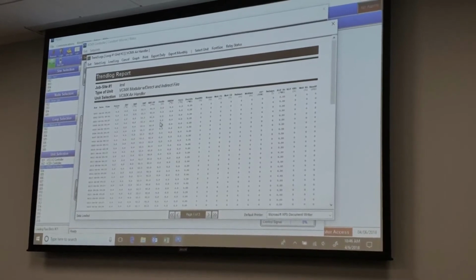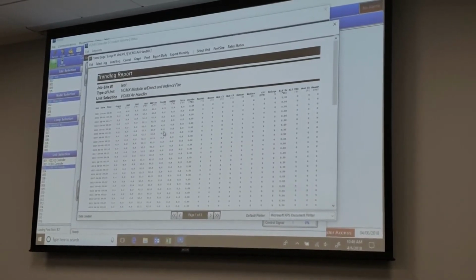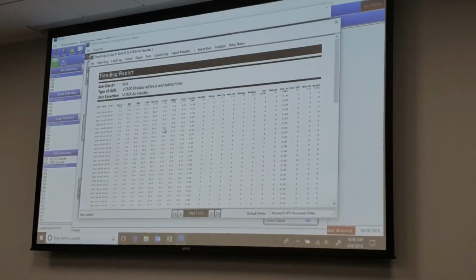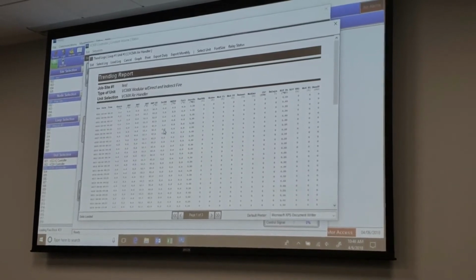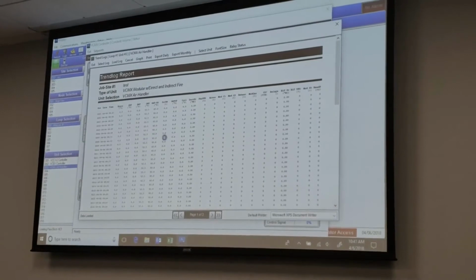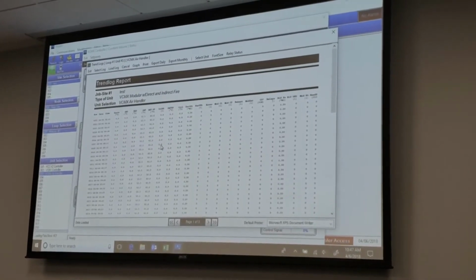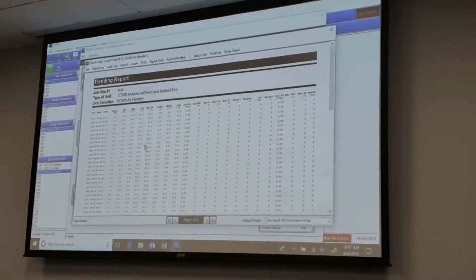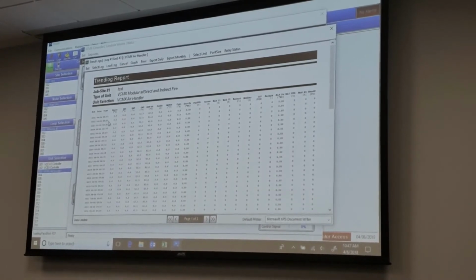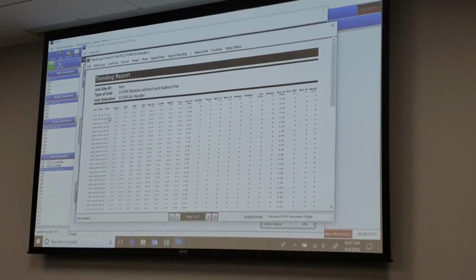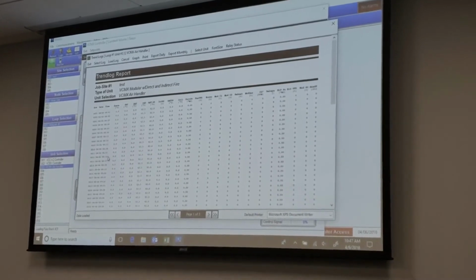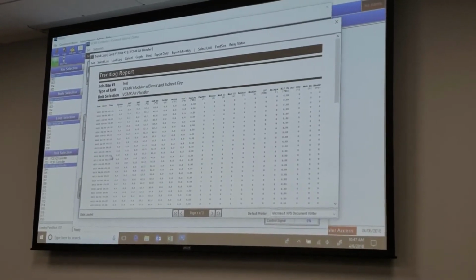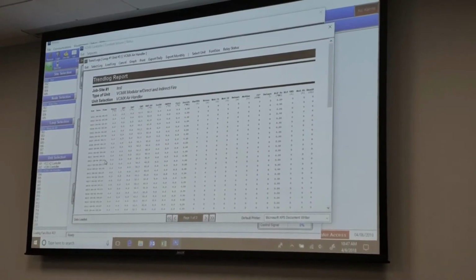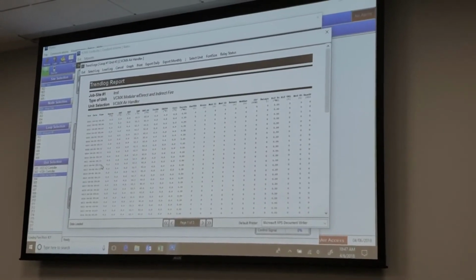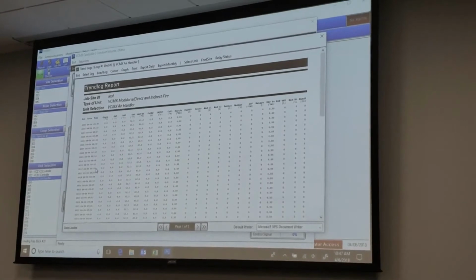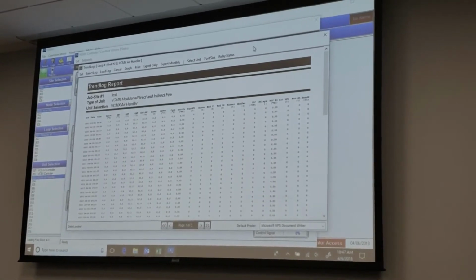Indoor RH, same thing. My RH sensor was reading correctly, and then something happened, and it shot up. What happened in the space that caused it to do that? One of the things that I always look at is the minutes, looking at the time. I actually had a job site where an electrician kept going out there, and he was doing something, and our unit was shutting down, and the guys were saying, "Your unit's shutting down." And I looked at the power up counts.